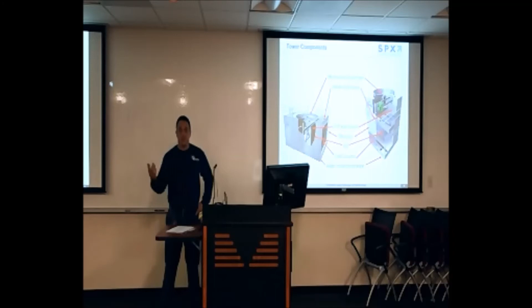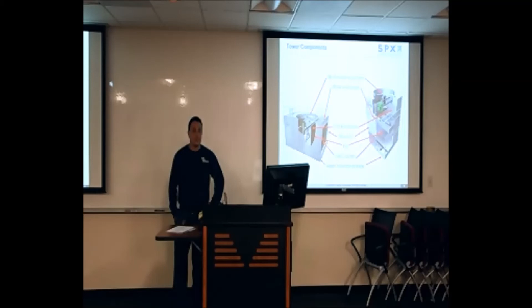A lot of times, what I have found is when the drive trips on ground fault, the technician will just put in a bypass, and then they'll end up blowing out the bypass components. That's usually the technician doing that. They didn't megger the motor before they went ahead and did that. So if you have any questions, that's pretty much it. You guys pretty much all got this one covered, from what I've noticed. You guys good? All right.